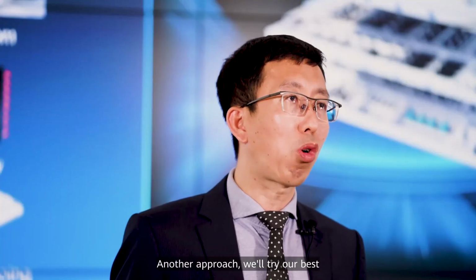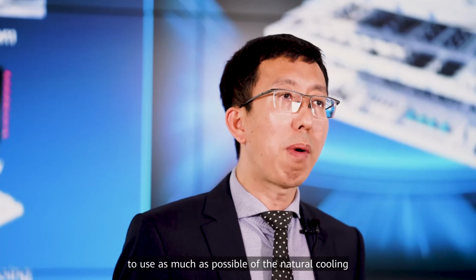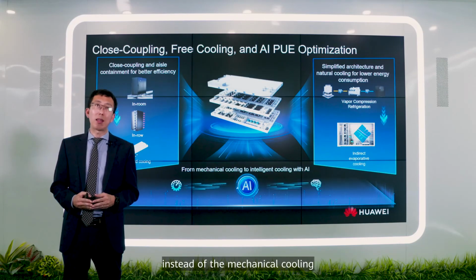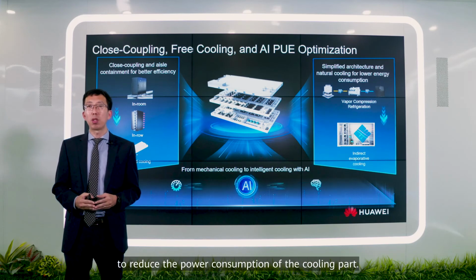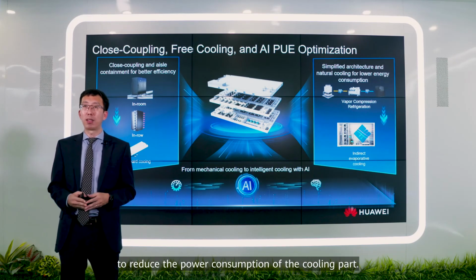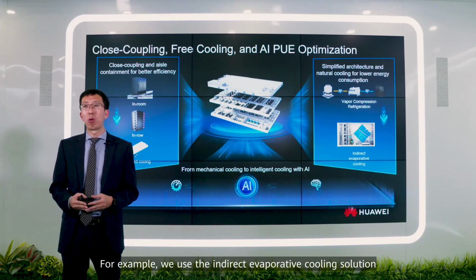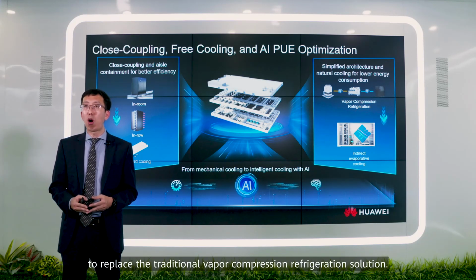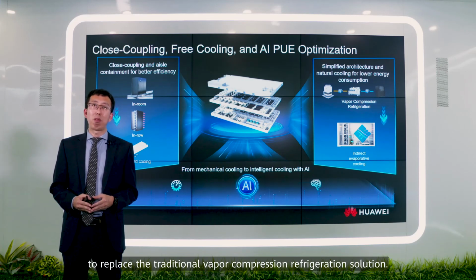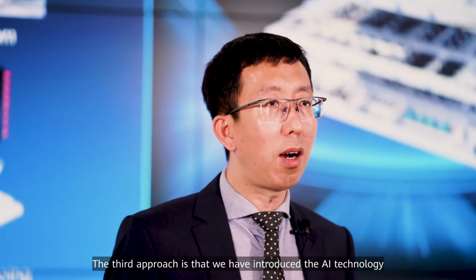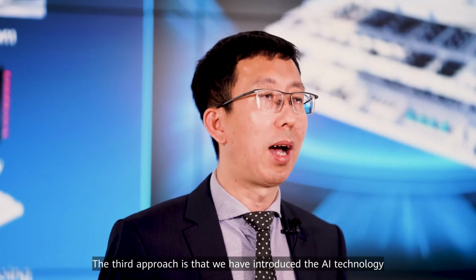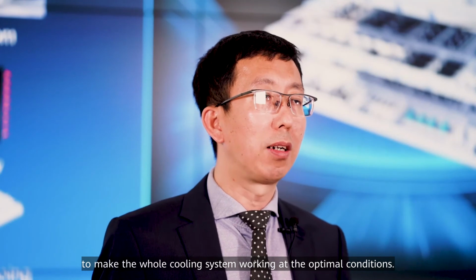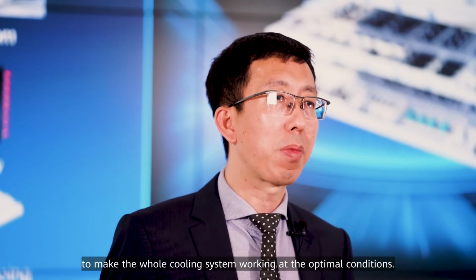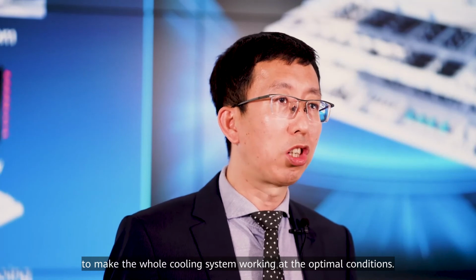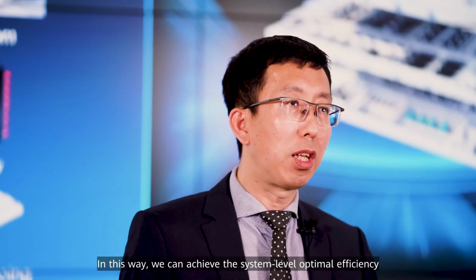Another approach is to use as much natural cooling as possible instead of mechanical cooling to reduce power consumption, for example using indirect evaporative solutions to replace traditional vapor compression refrigeration solutions. The third approach introduces AI technology to make the whole cooling system work at optimum conditions, achieving system level optimum efficiency for the whole data center.